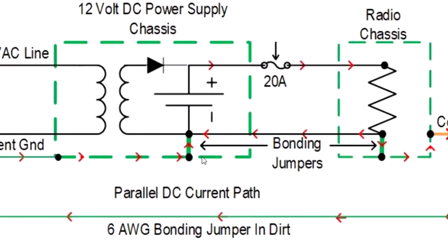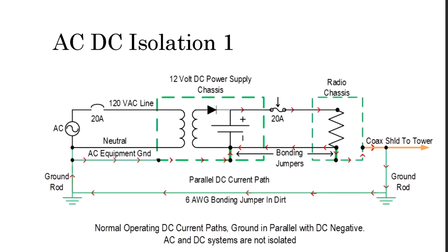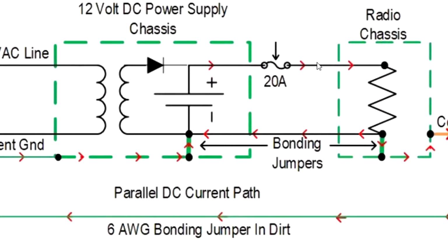Now, on the industrial and commercial side of radios, we do bond the battery, but we bond the positive, because if you bond the positive, you don't have corrosion on the system. You actually have galvanic protection. So I think you can clearly see the problem, and the result is you bonded the grounded circuit conductor twice. That forces ground to be in parallel with it.